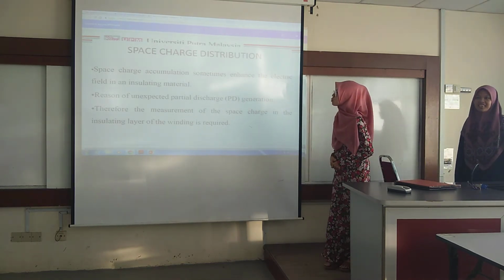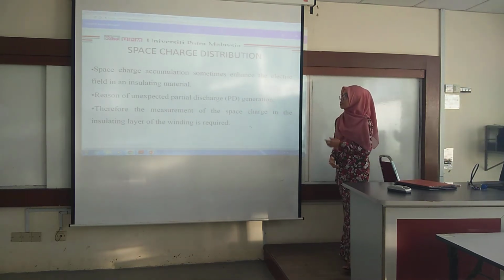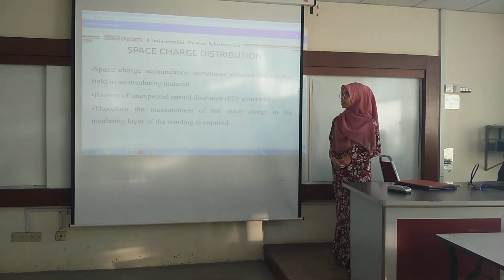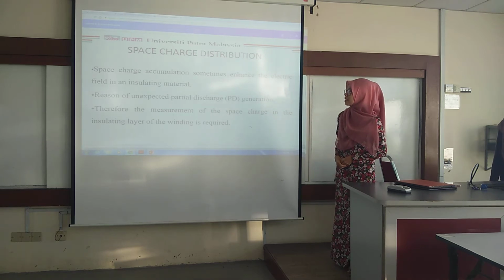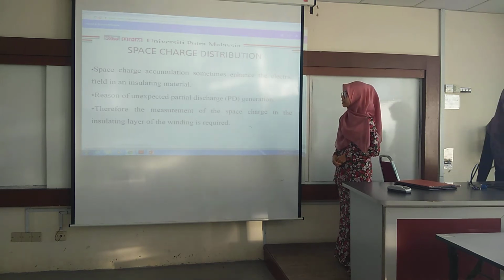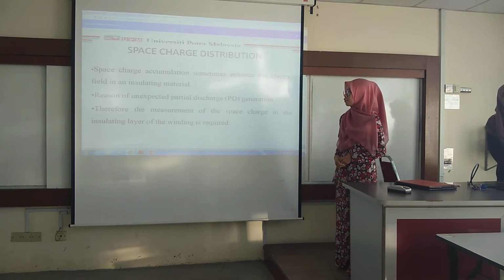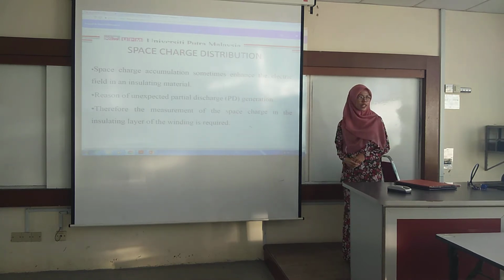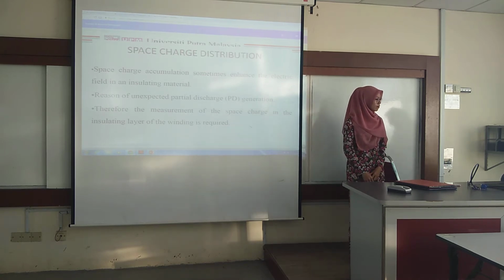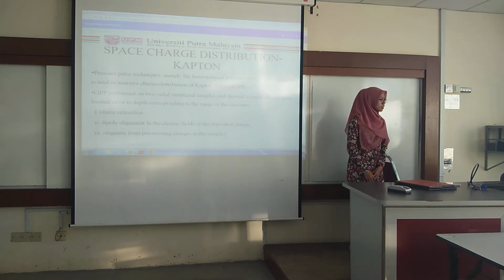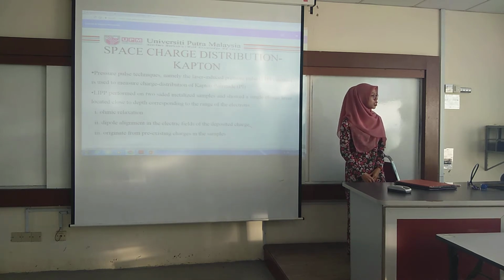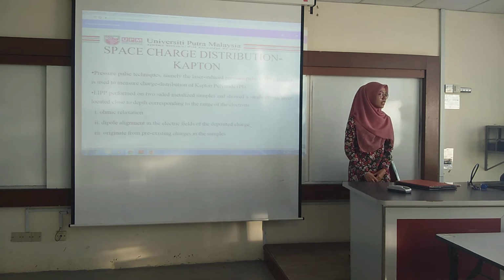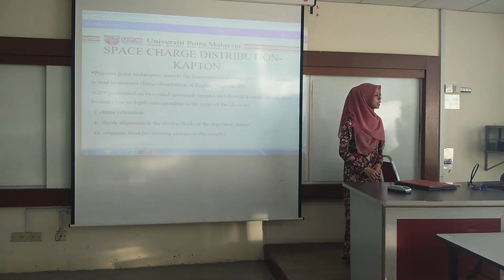Next, I will proceed to space charge distribution. Space charge accumulation sometimes enhances the electric field in insulating material, and it can result in unexpected partial discharge generation. Therefore, the measurement of the space charge in the insulating layer of the winding is required.